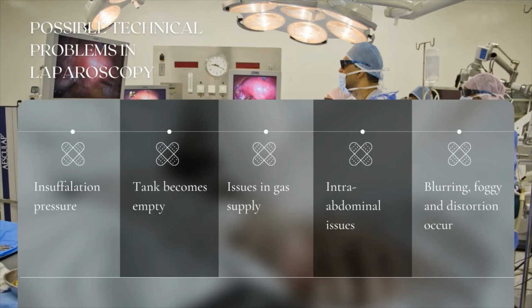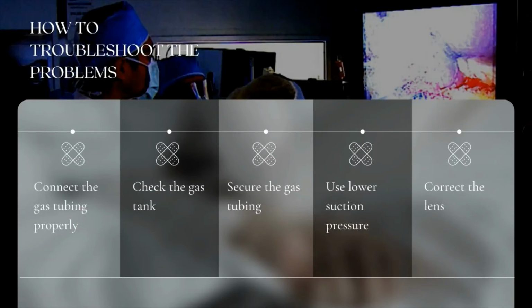Sometimes the picture is not clearly displayed on the monitor. This is due to a power-off or sudden loss of the light source. Poor image quality can occur due to the light, with blurring, fogging, and distortion. These are the troubles that occur in the laparoscope or during laparoscopy. Next, how to troubleshoot these problems. Connect the gas tubing properly before the procedure. Check the gas tank properly.